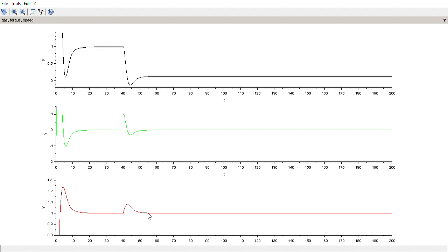The torque, when you open the breaker, it's going to be instantaneous. It's going to pop up, which is why the speed starts to come up. But as you cut back on fuel, the torque's going to go down. There's an overshoot on torque and on fuel, right? Which, like I said, if my model was better, I would take that out. And the speed comes back down.